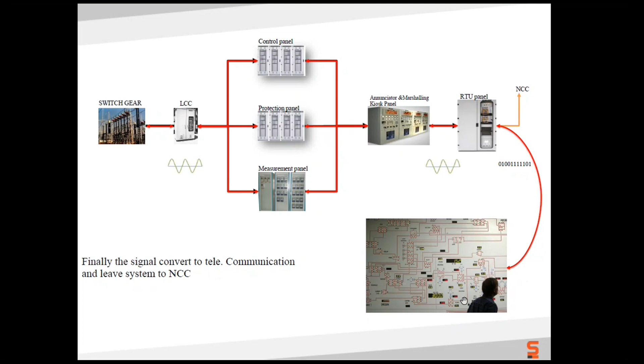So in an SAS based substation, the LCC (Local Control Cabinet) remains the same, because a local cabinet will always be there with a breaker. Suppose some problem is there in the link or the cable has cut, LCC is always present in every equipment. You will find a local button to operate that equipment, or a remote mode. This is available in every equipment: breaker, CT, CVT, HVDC pumps, HVDC valve hall, earthing, DC side, DC switches. In HVDC we have a lot of DC switches. So every equipment has a remote option and a local option. LCC is there.